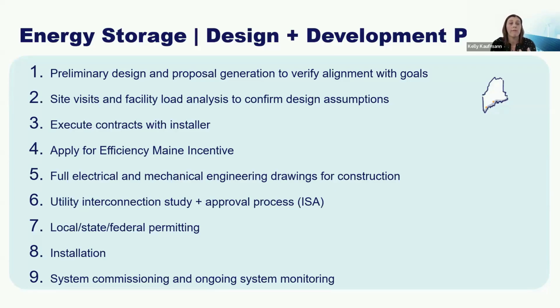You'll want to make sure you get full electrical and mechanical engineering that goes into the construction set. The utility interconnection process can be a bit daunting if you haven't gone through it before, and depending on system size, you may need to go through some form of interconnection study to ensure your system's capacity doesn't exceed the eligible capacity of your substation.